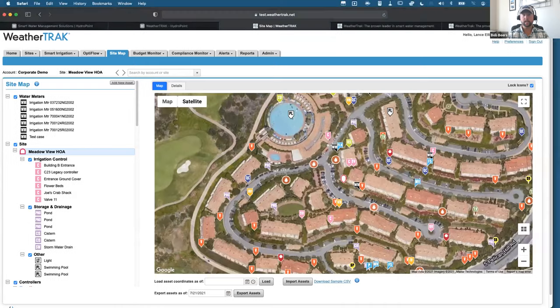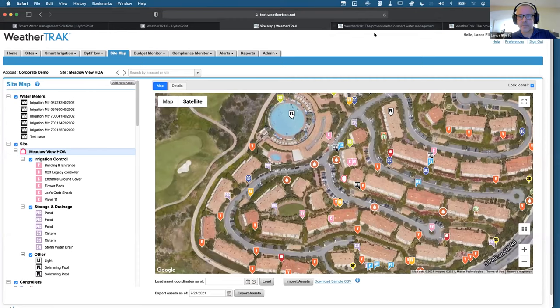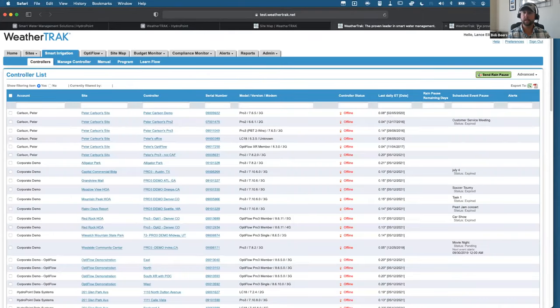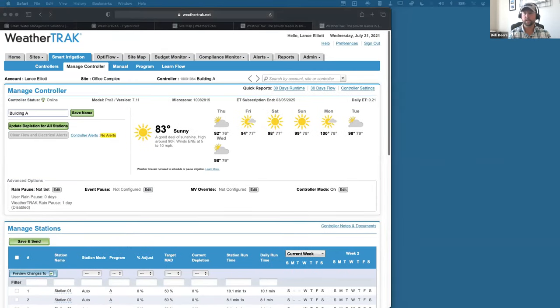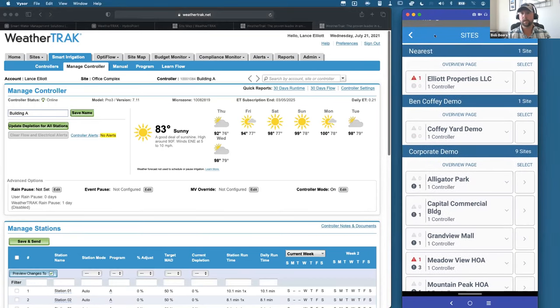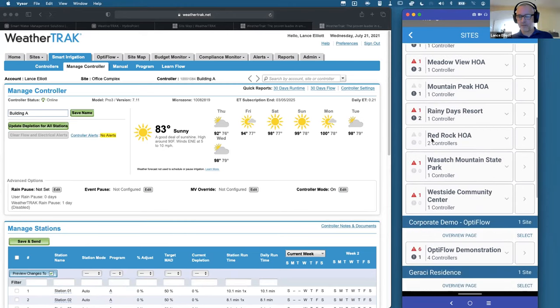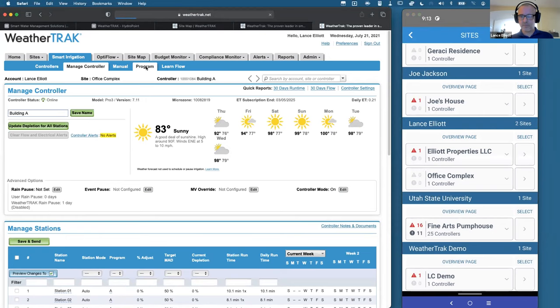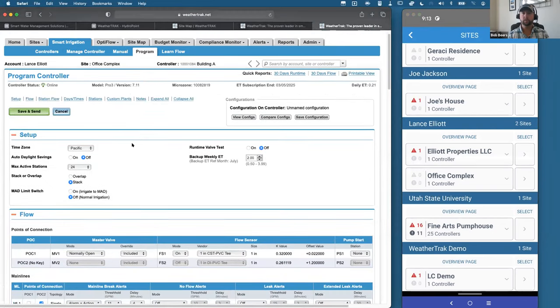Part of the reason for releasing mobile 3.5 alongside the 200-station controller: this will be the first time OptiFlow ships from the factory already in its OptiFlow mode, on firmware base 8.9. The mobile app can now program the entire controller — all station programming and program times — up until the hydraulic tree. This provides much of the panel functionality that previously required pressing many buttons at the controller itself, making setup far easier and more intuitive.